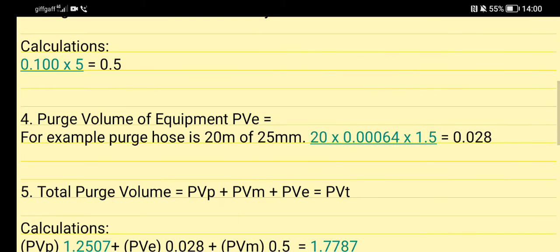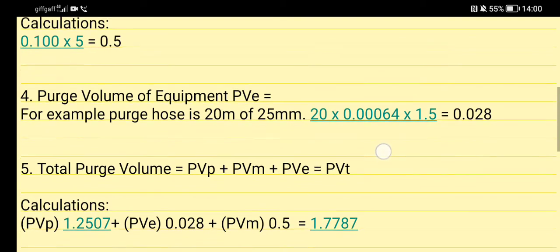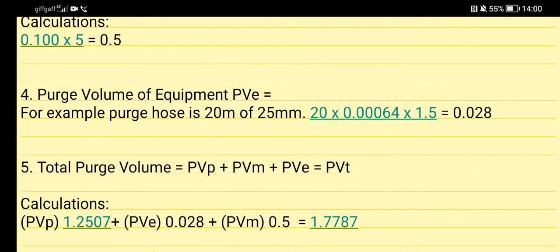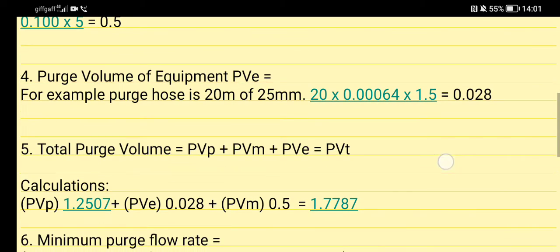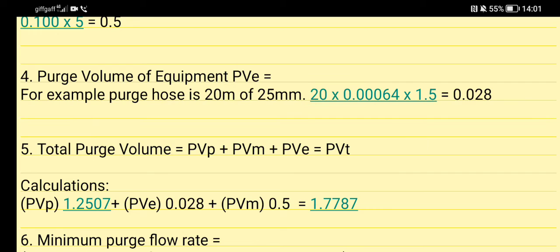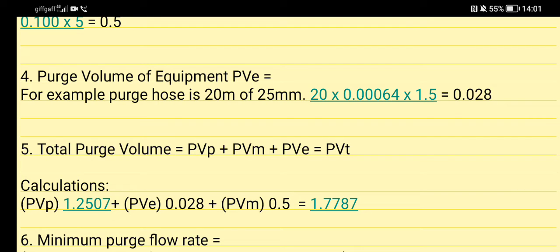Then we move on to stage 4. Now we need purge volume of equipment PVE. For example, if your purge hose is 20 meters long and it's 25 millimeters in diameter, the bore, you get 20 times - and then I've got this value here from my chart, similar to the tightness test chart of getting your volume. You've got your volume, then you times that by 1.5, and then you'll get 0.028.